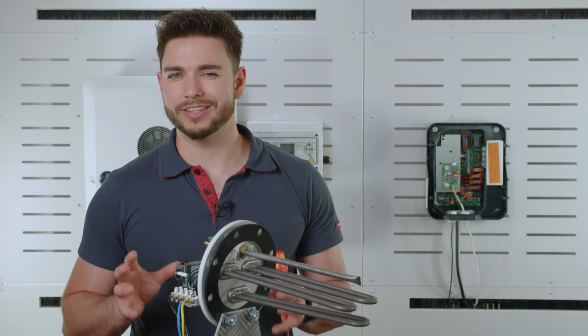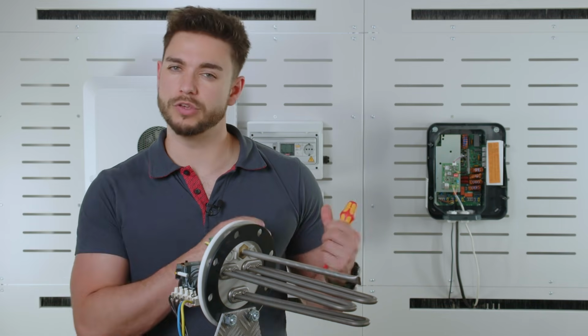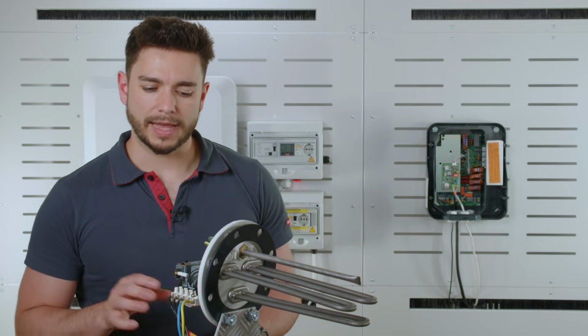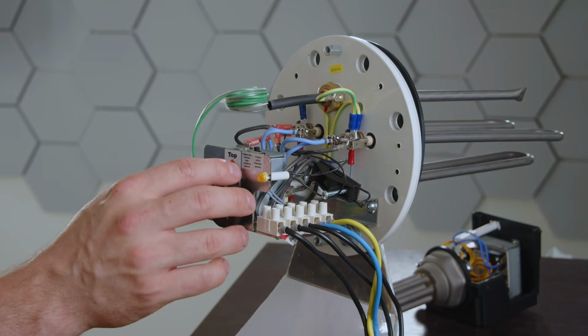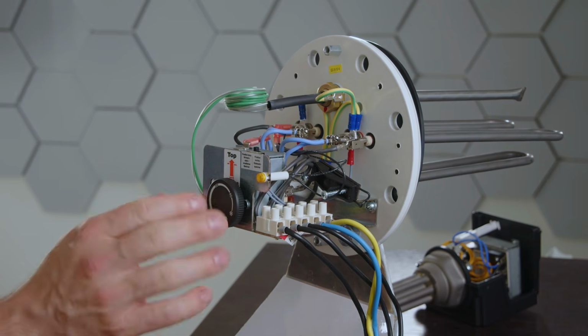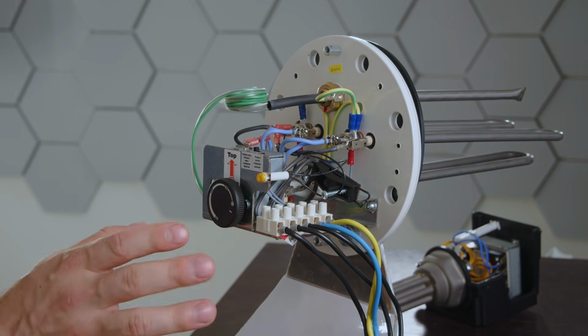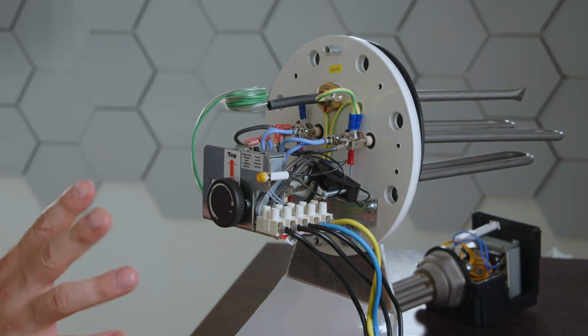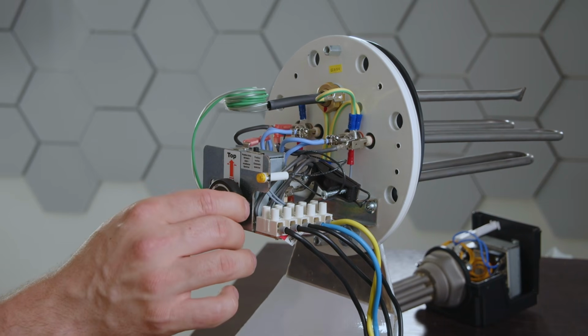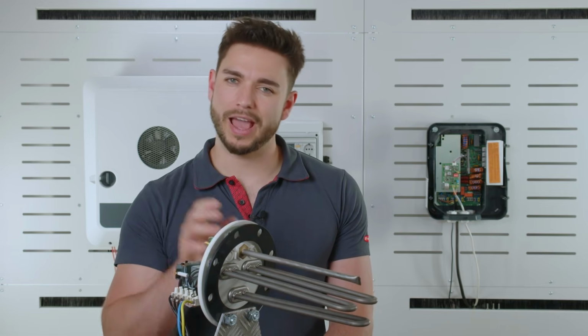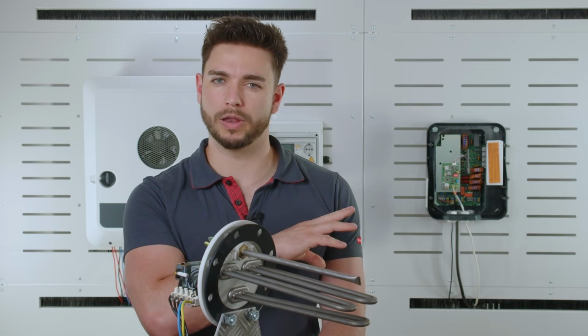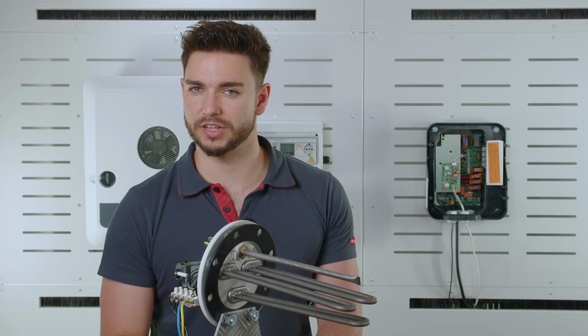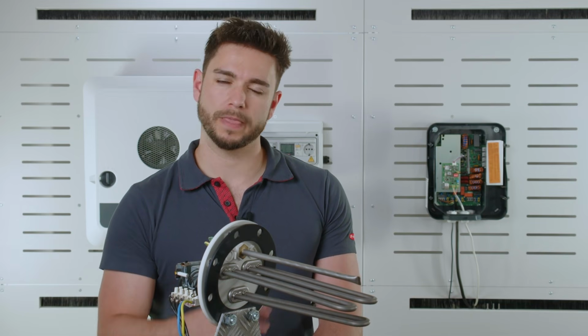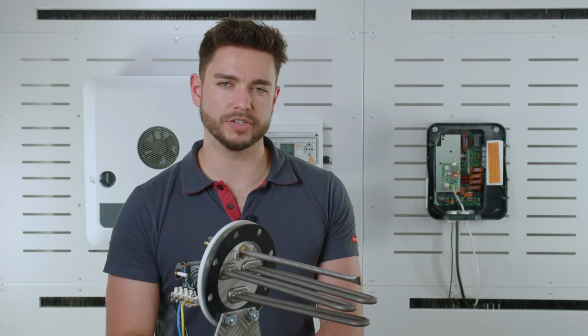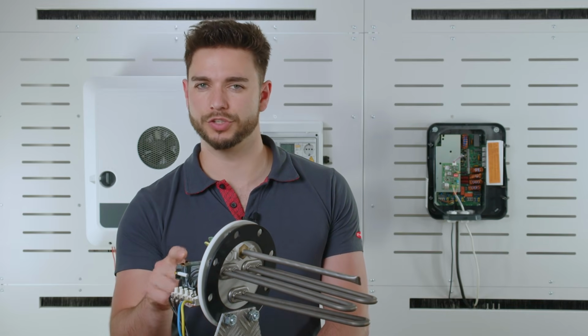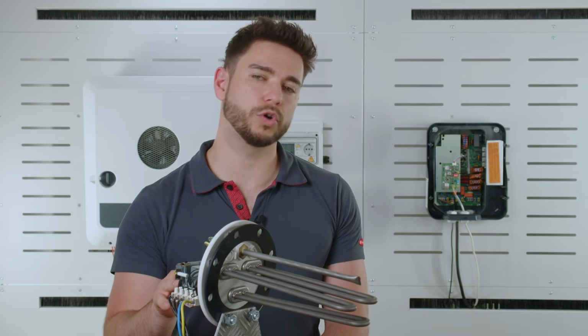So you already see, the simpler the heating rod, the better it is for the usage of the Ohmpilot. Last but not least, there is always a question about the bimetal sensors, the mechanical temperature sensors out here. No problem, these do not count. Also LEDs like this, that's not a problem. You simply want to set it a little bit higher for the temperature rating, as you would have the temperature rating within the Ohmpilot if you use, for example, a temperature sensor, the PT1000. So if I want my temperature to reach up to 50 degrees in the boiler, I want to set this a little higher, to 55 let's say, because otherwise it would switch off first.